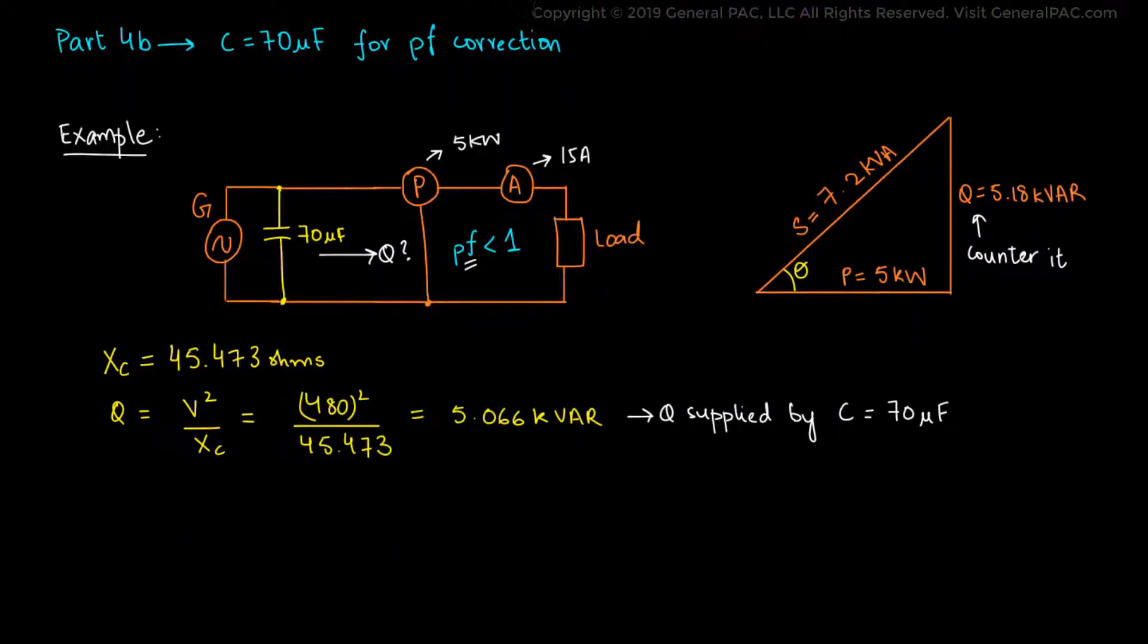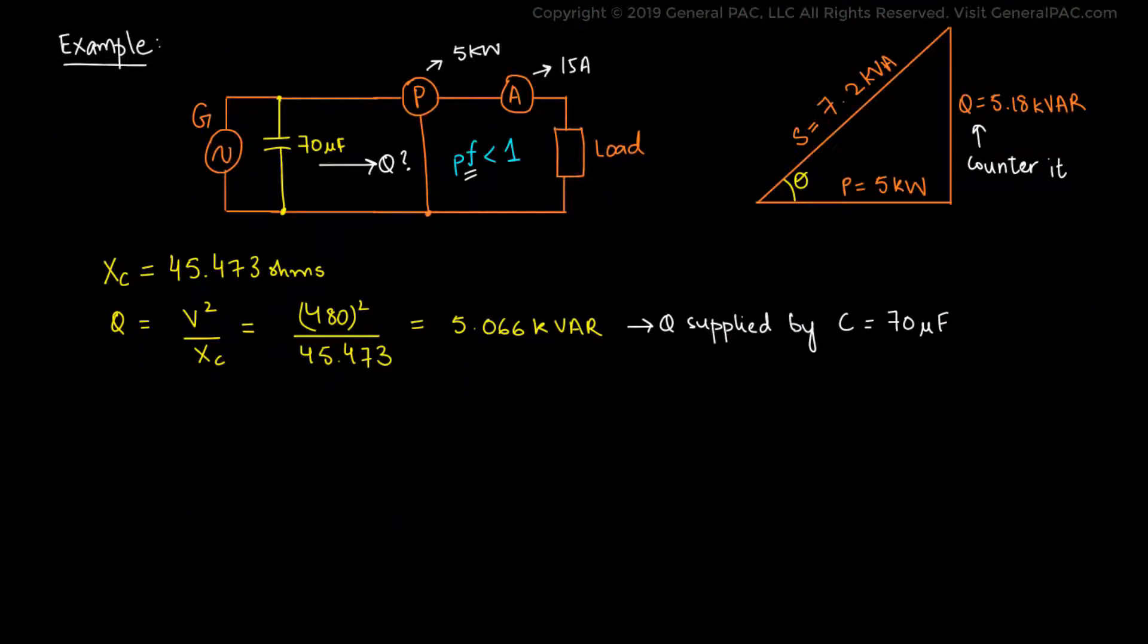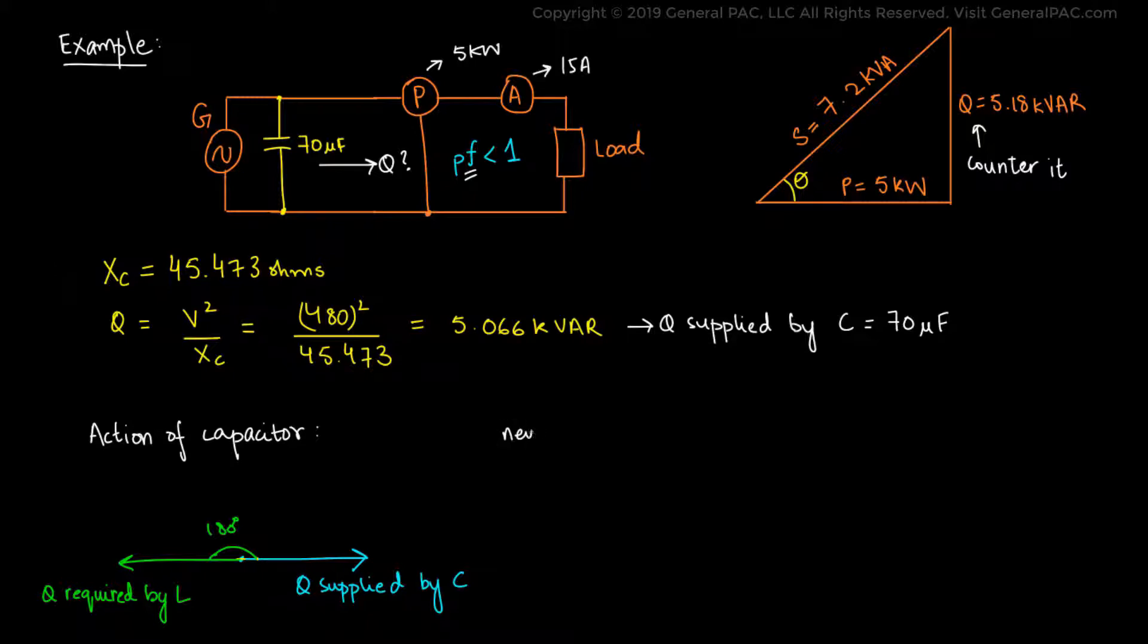Recalling the operating mechanism of the capacitor, we can see that the phase angle of the reactive power supplied by the capacitor will be 180 degrees out of phase from the reactive power required by the inductive load. And that's the really important part. Therefore, it will be directly opposing its effect. Mathematically, we can subtract both quantities to get the reactive power of the system. So the reactive power is equal to 5.18 kVAR minus 5.066 kVAR, and that equals 0.114 kVAR.